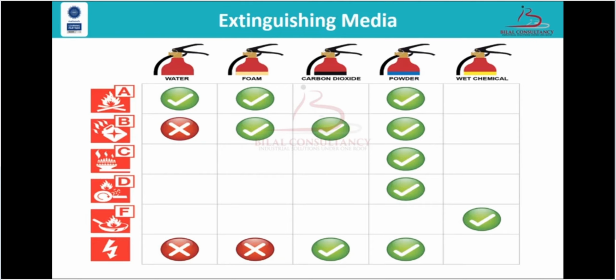Carbon dioxide fire extinguisher. They are suitable for class B fires and electrical fire. It works by smothering the fire. It is not suitable for use on class D or F fire. It must be used with care because the body of the fire extinguisher gets very cold during use and can cause freeze burn injury. CO2 is an asphyxiant gas, and so care must be exercised when using it in an enclosed space.